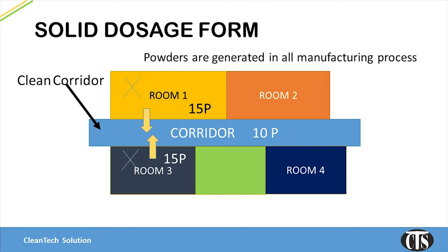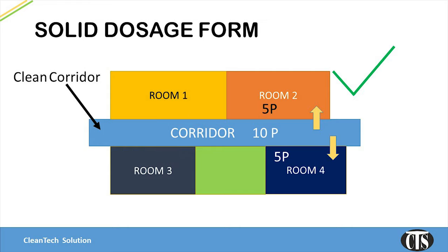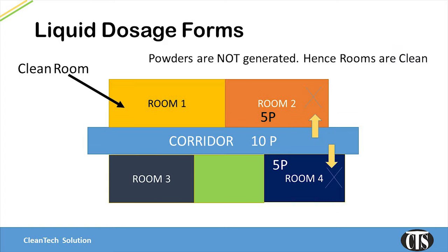Now let us consider an area where oral solid dosage forms are manufactured. According to regulatory guidelines, the room has to be supplied with air through a HEPA filter. A manufacturing area for OSD will have lots of particles constantly generated during the OSD manufacturing process. If the corridor has a lower pressure compared to the room, air from the room will move into the corridor when doors are opened, contaminating the corridor with particles and causing cross-contamination. Hence, in OSD manufacturing, corridors are kept at higher pressure and rooms at lower pressure. Where liquid dosage forms are manufactured, powders are not generally generated. Hence, liquid processing rooms are classified as clean areas and corridors are unclean or dirty areas.